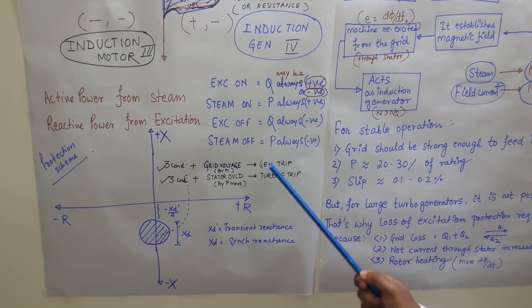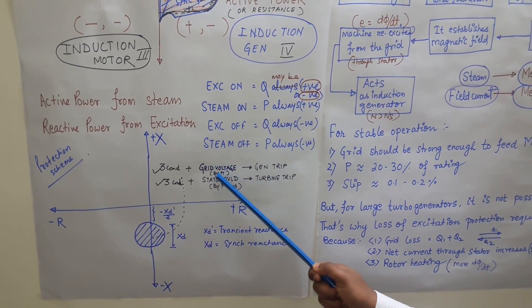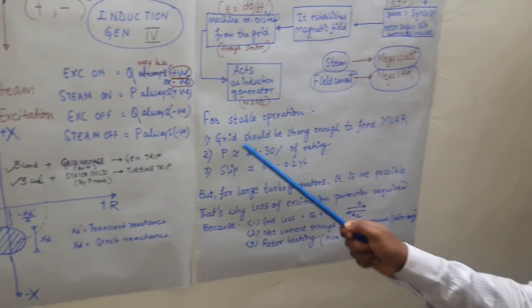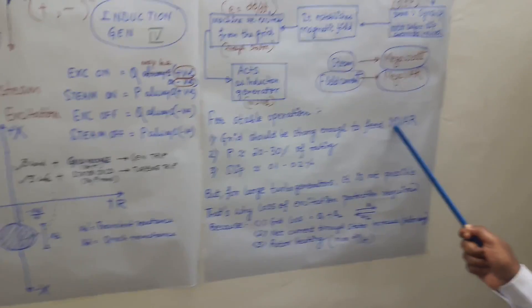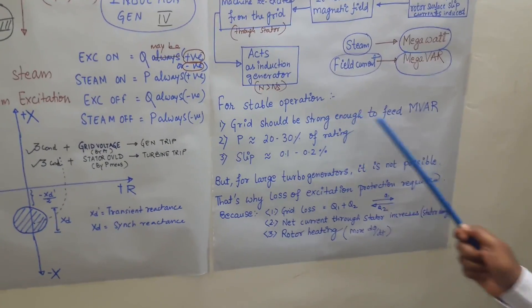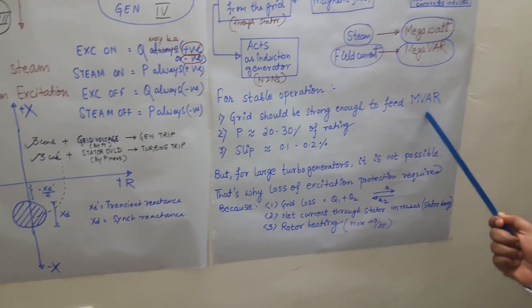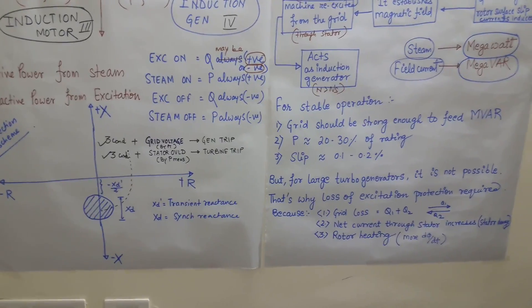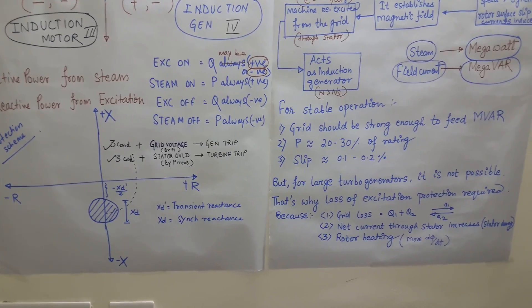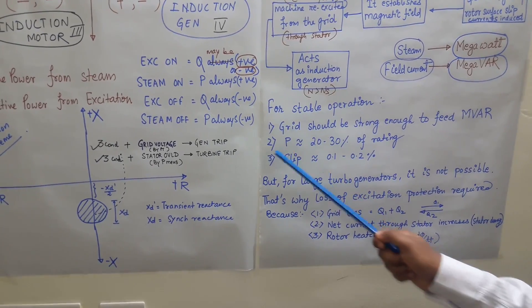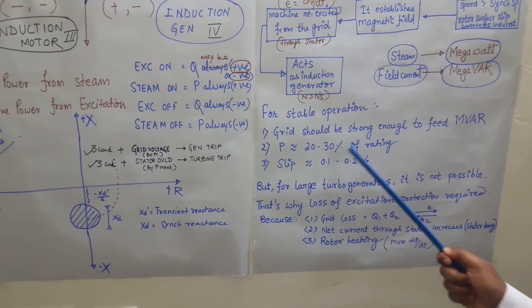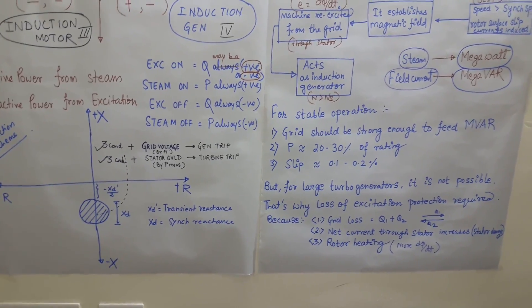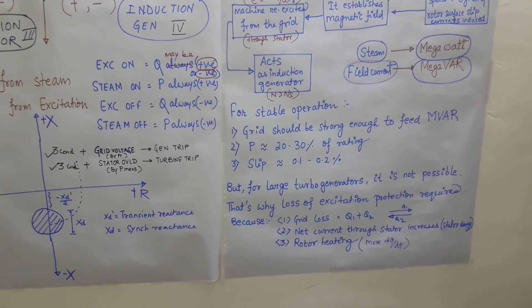The reason for considering a generator trip when grid voltage falls is that if the grid is not able to supply reactive power (MVAR), the grid voltage will fall and the grid may collapse, leading to a blackout. The second condition is related to the overloading of the stator, so we can wait for the turbine trip followed by the generator trip.